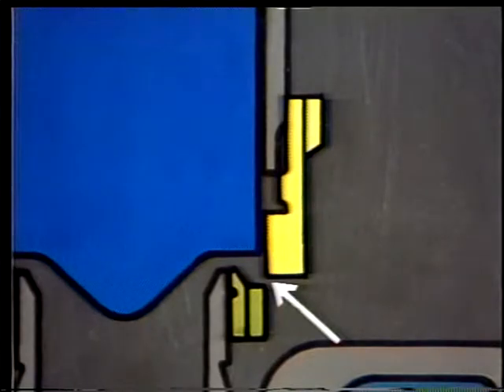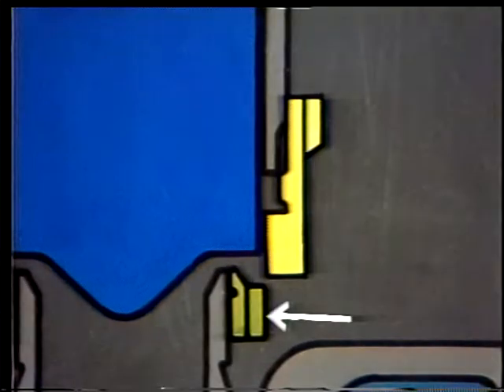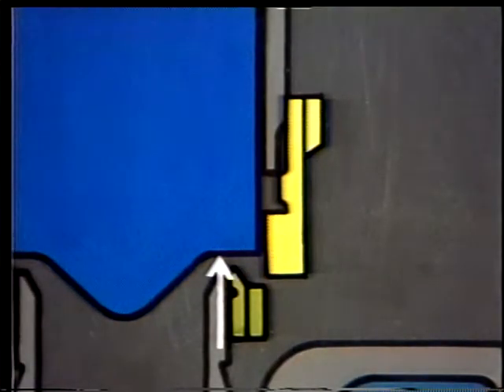In exactly the same way, pressurized gas or steam directed downward by the upper ring will exert an upward force on the disc. So, in its lower position, the upper ring not only narrows the escape route of the steam, but also helps to create a reactive force. The end result is a greater blowdown of the valve. The lower ring also has two jobs. It directs escaping steam directly at the disc, ensuring a clean, forceful popping action. And it traps a cushion of steam that softens metal-to-metal contact when the valve closes.